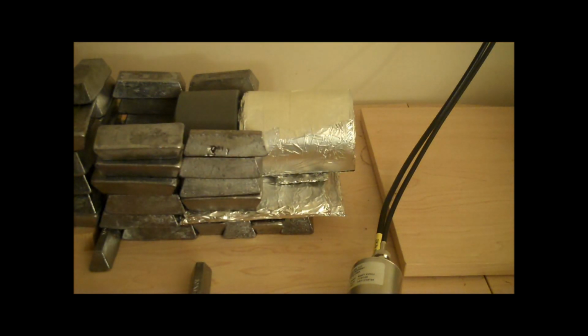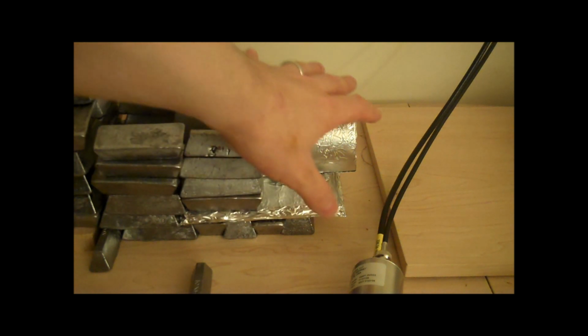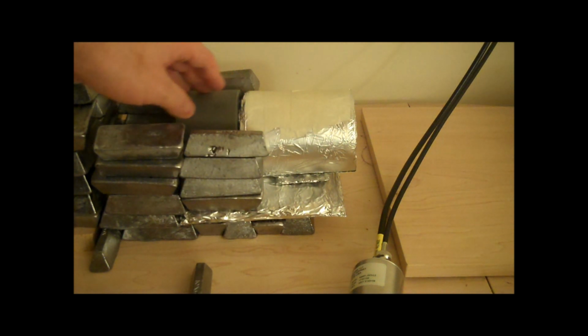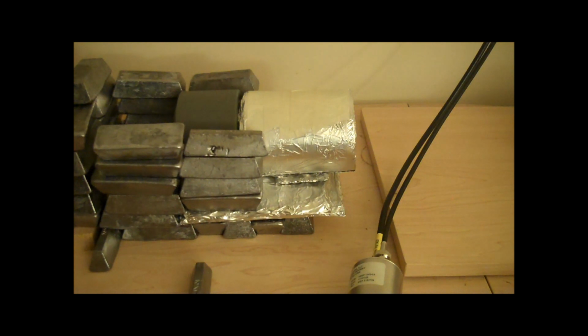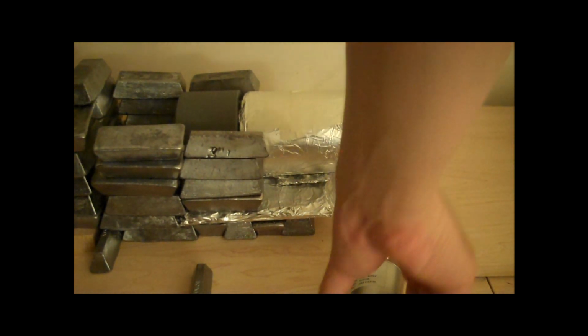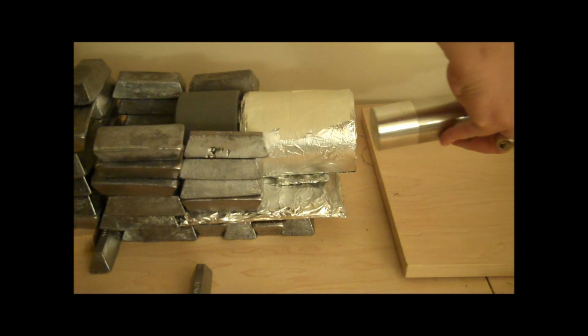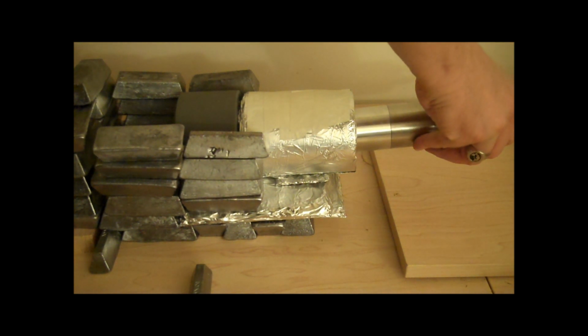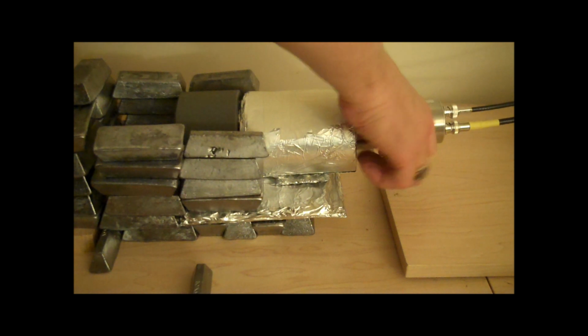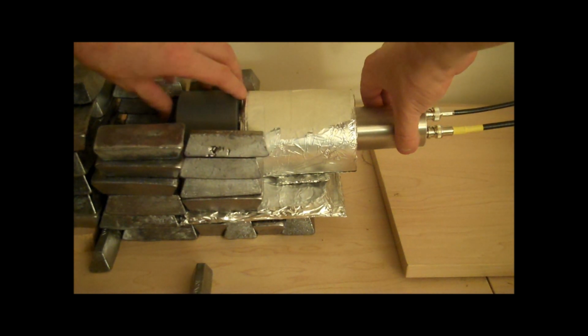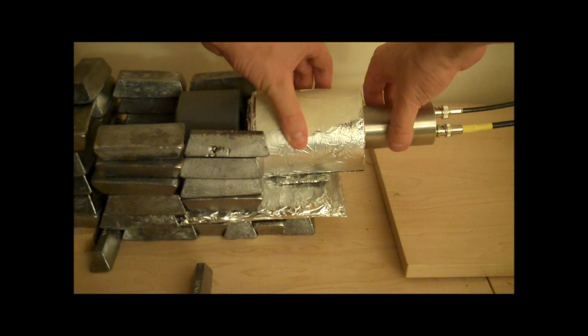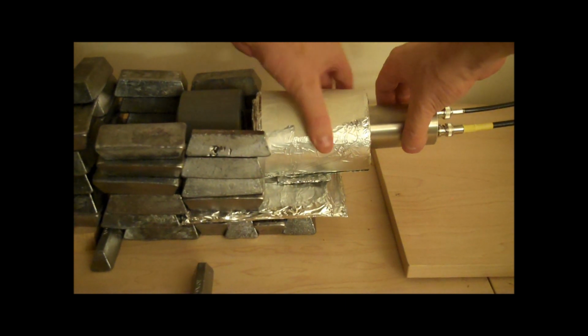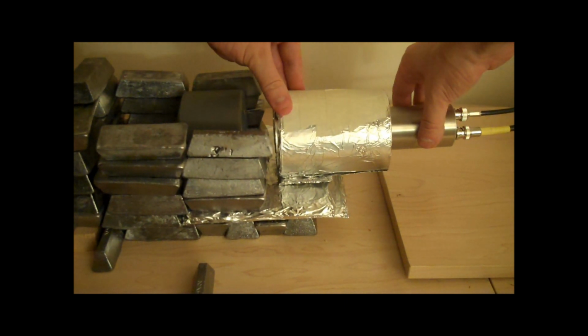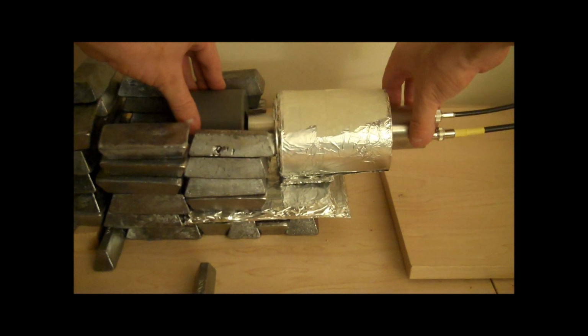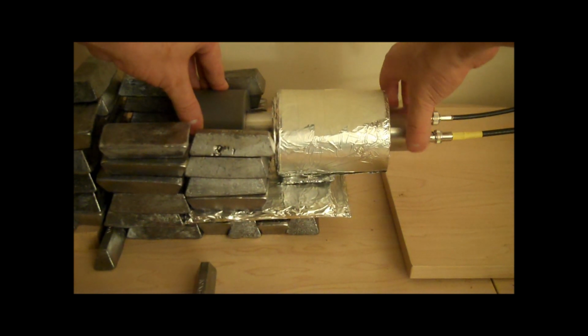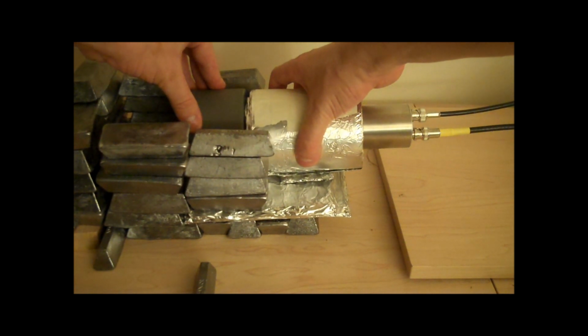We will now take the scintillator and load it into the scintillation chamber right here. These are large pieces of lead, thick lead, greater than an inch, to prevent background radiation. The scintillator must be very carefully inserted into its housing to ensure that nothing happens to it. It is a very delicate piece of equipment, to say the least. This equipment was form-fitted for the scintillator very, very painstakingly and by hand.